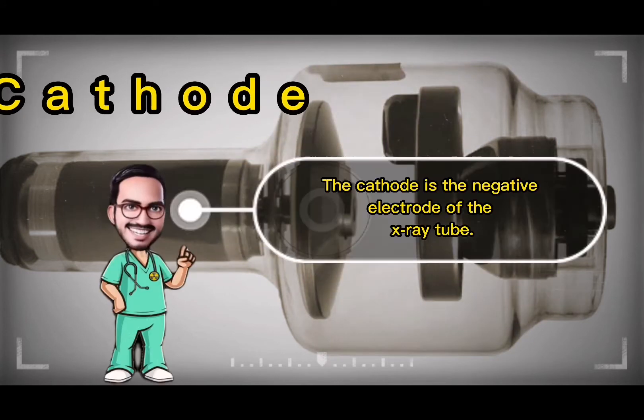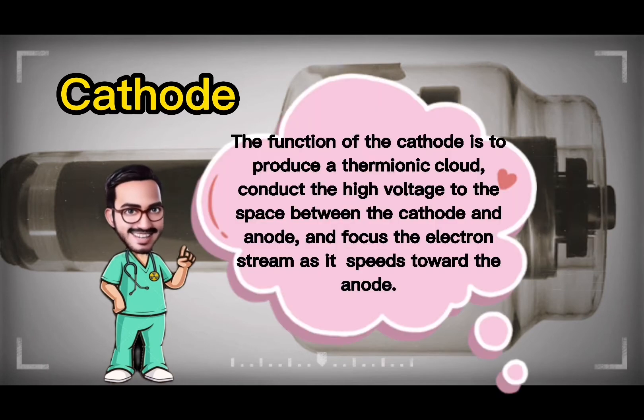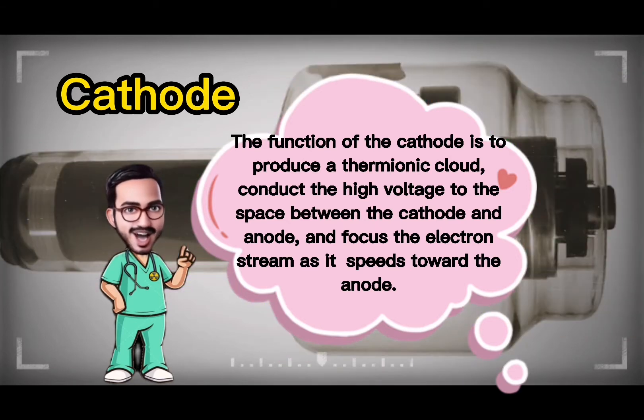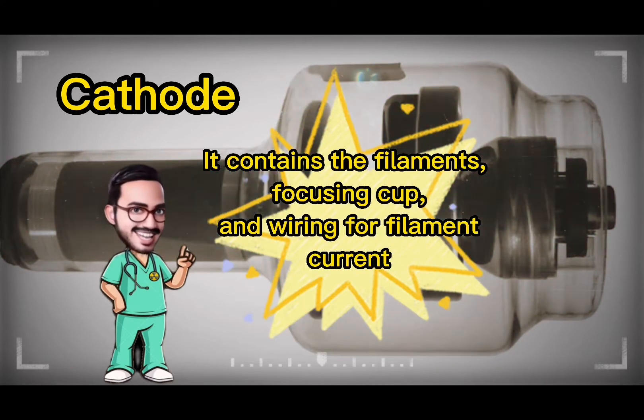The cathode is the negative electrode of the x-ray tube. The function of the cathode is to produce a thermionic cloud, conduct the high voltage to the space between the cathode and anode, and focus the electron stream as it speeds toward the anode. It contains the filaments, focusing cup, and wiring for filament current.